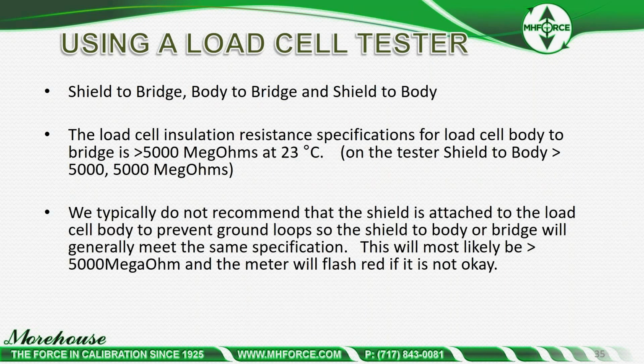You can use a tester to test shield to bridge and shield to body. The load cell insulation resistance specification for load cell body to bridge is typically greater than 5,000 megohms at 23C. On the tester, shield to body is greater than 5,000 megohms. We typically do not recommend that the shield is attached to the load cell body, to prevent ground loops, so the shield to body or bridge will generally meet the same specification. This will most likely be greater than 5,000 megohms, and the meter will flash red if it's not okay. So that's typically how you use a load cell tester.